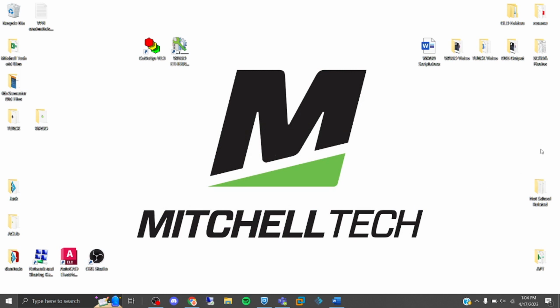If you just want to program it, you're going to need a couple of software packages: Wago Ethernet Settings and CoDeSys version 2.3.9 or higher. If you're in the SCADA lab, they should be on the S drive under the Wago folder. If not, I'll have a link for both in the description. Just request them and they should email them to you, but I was unable to get CoDeSys this way. They're trying to move people off of CoDeSys 2.3 onto 3.5, so I had to call Wago and they sent me the files.